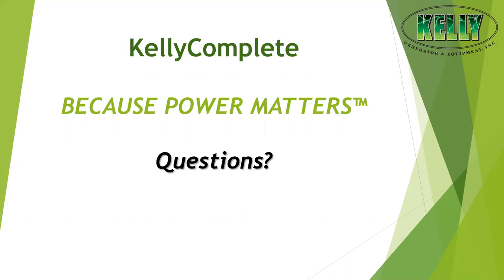That's really a question of which pieces of equipment can ride through an outage and which can't. For manufacturers, we typically put control systems on a UPS, as well as expensive machine tools where a hiccup could break tooling. But heavy loads like dryers and heaters can often go down for a minute or two. Discuss it with us and we can find a solution.